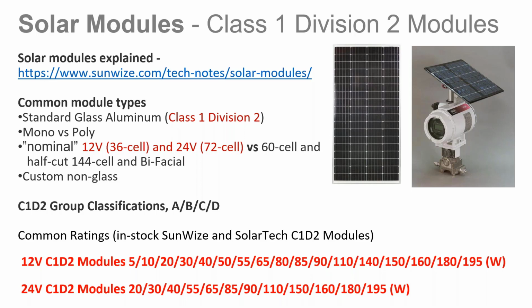As Brad alluded to, in the Class 1 Division 2 group classifications, we have these A, B, C, D groups. One thing I'll point out about that as it relates to solar modules on the next slide - but before that, at the bottom you'll see some rough capacity ratings for commonly available Class 1 Division 2 solar modules. Different manufacturers and distributors may have slightly different variations, but this gives you a feeling for what types of module ratings can be ordered with a Class 1 Division 2 certification, either as a nominal 12 volt or a nominal 24 volt.